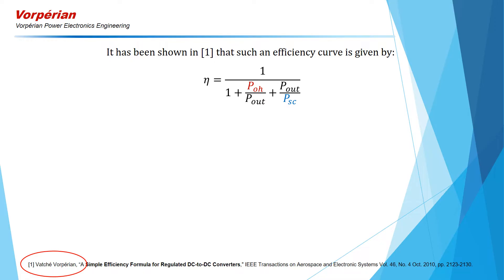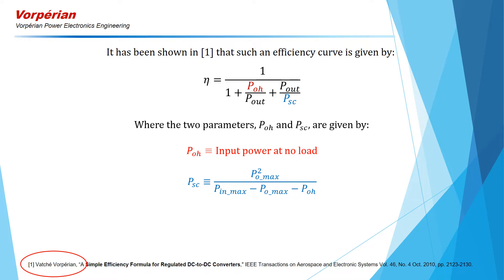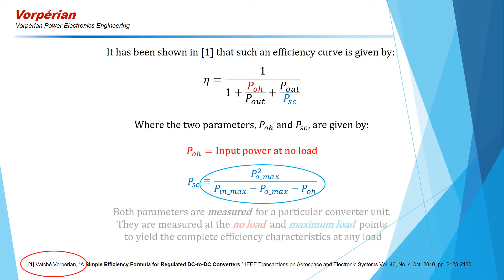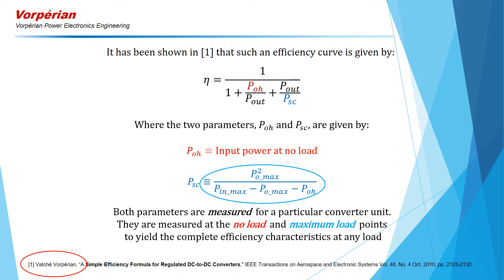In this equation, POH and PSC are two parameters defined as follows. POH is the measured input power at no load, and PSC is related to the measured maximum power by this equation. It is important to emphasize that both of these parameters are measured on a converter unit and not computed from first principles for a particular converter design. They are measured at two points: the maximum load point and the no load point. Once these parameters are inserted in the efficiency formula, the efficiency at any load can be obtained, as we shall see in the next example.